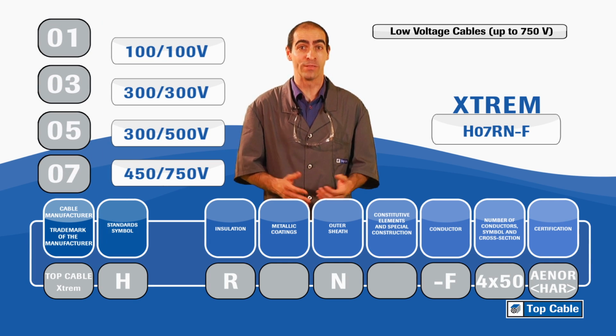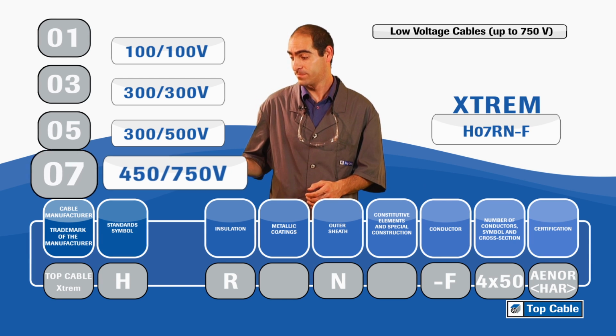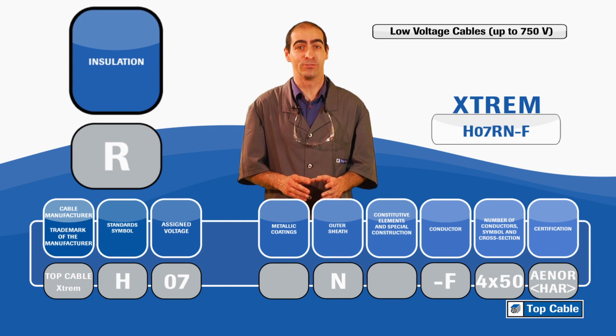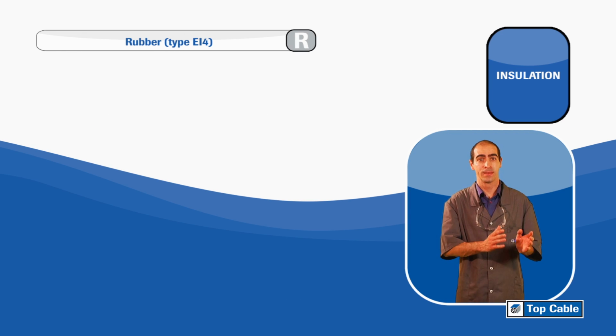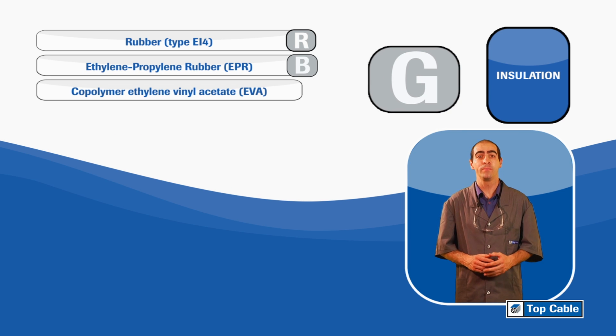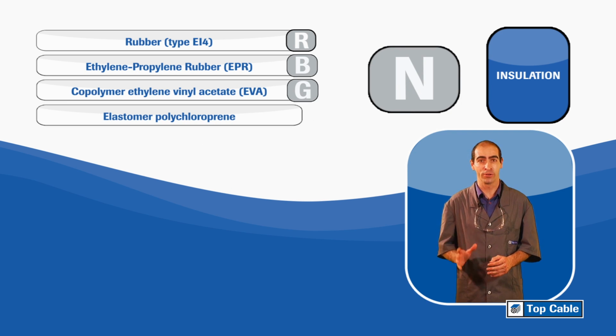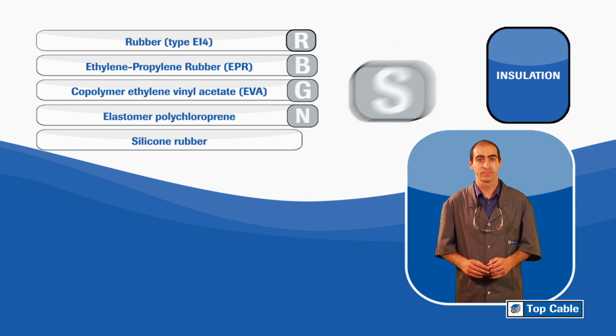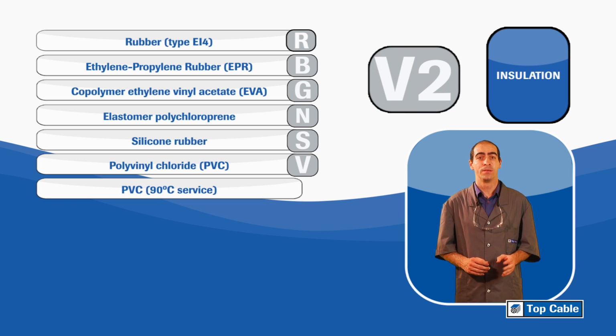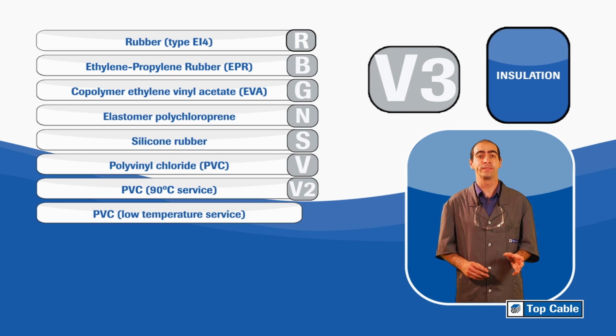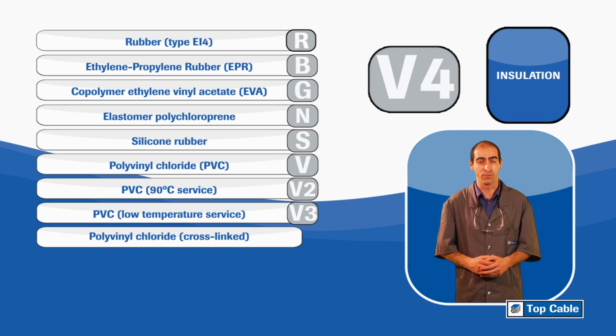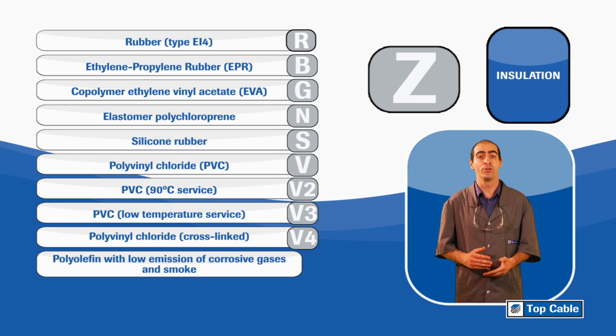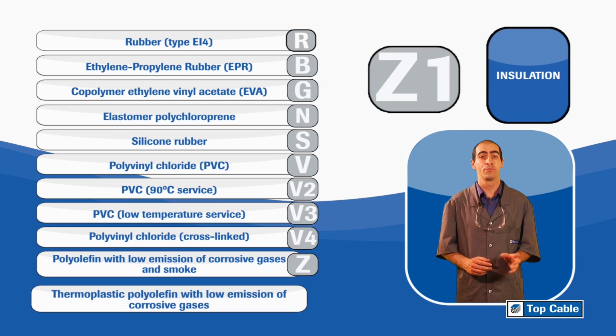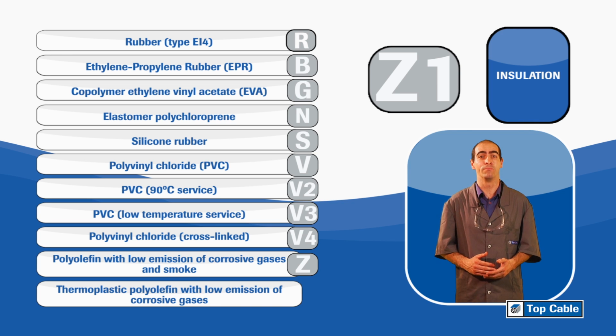Our H07RN-F is a 750 volts cable. R refers to cable insulation. In this case, it is a rubber cable. Other possible insulation types are B, ethylene propylene rubber, EPR, G, copolymer ethylene vinyl acetate, EVA, N, elastomer polychloroprene, S, silicon rubber, V, polyvinyl chloride, PVC, V2, PVC 90 degrees centigrade service, V3, PVC low temperature service, V4, polyvinyl chloride, cross-linked, Z, polyolefin with low emission of corrosive gases and smoke, Z1, thermoplastic polyolefin with low emission of corrosive gases.